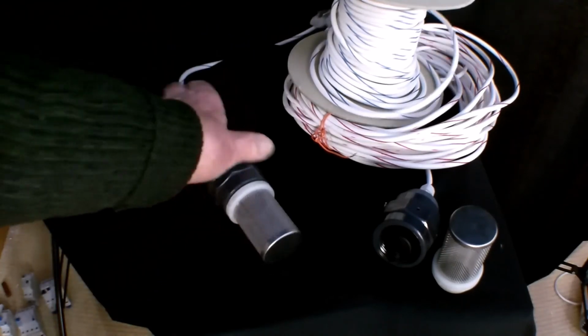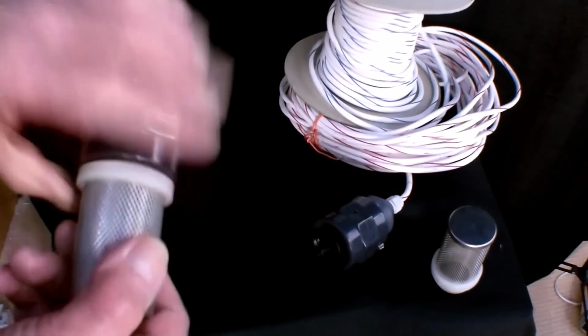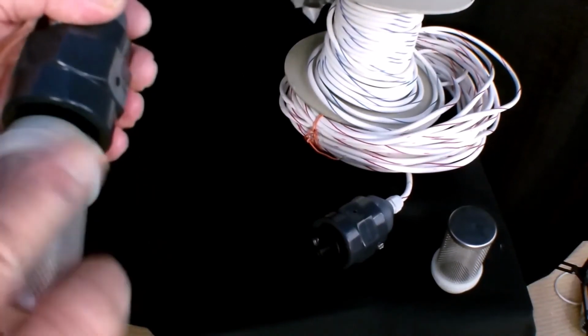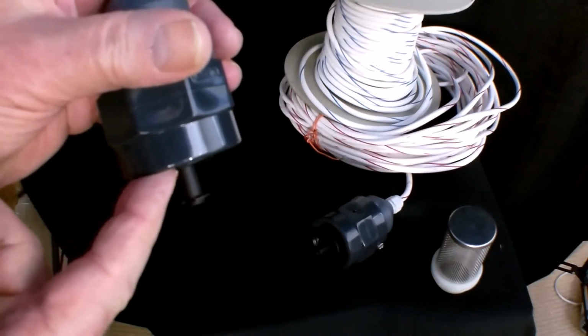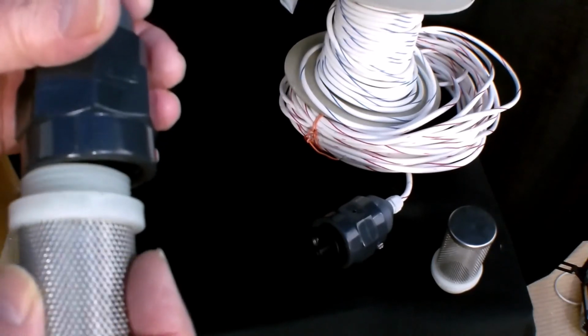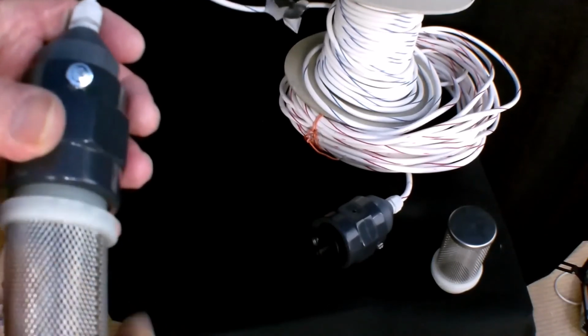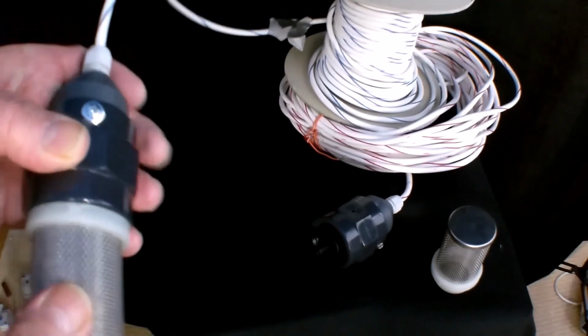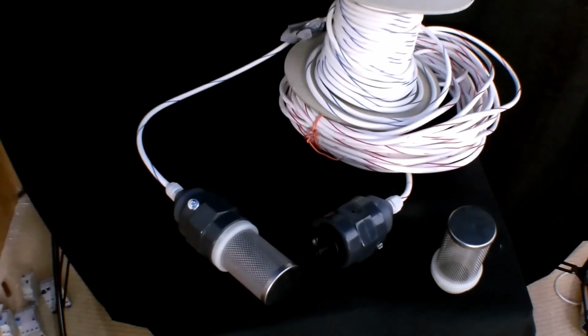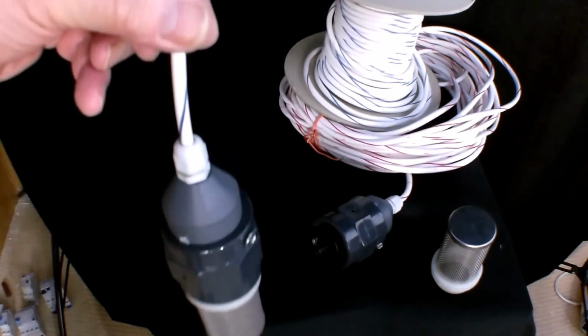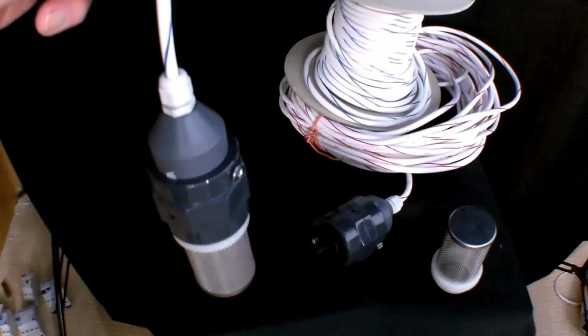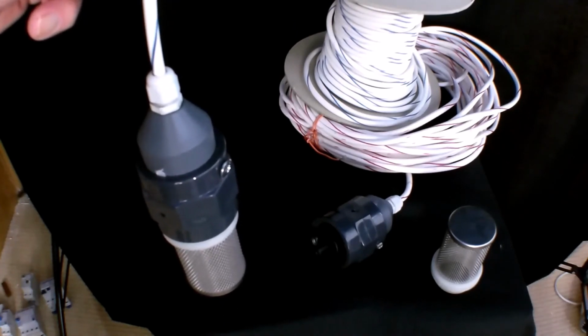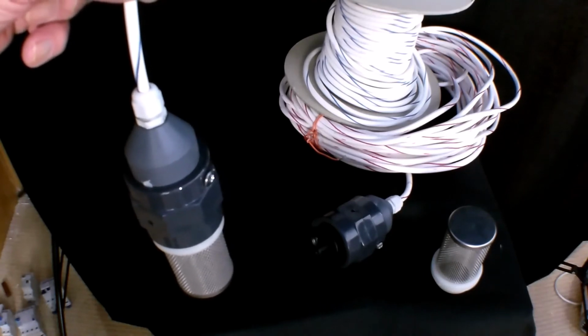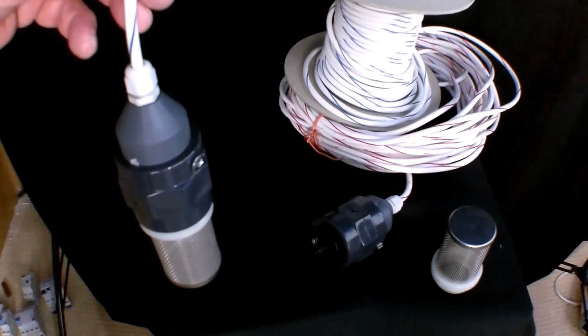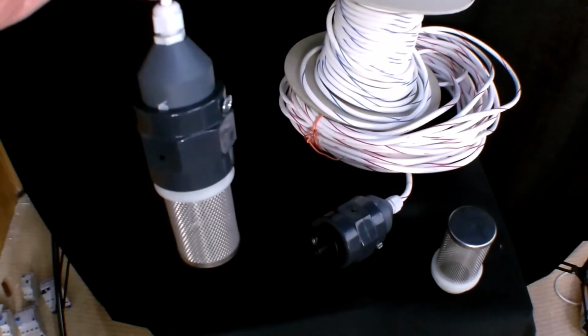The one over here is shown with the, I'll have to take it off here. This screen protects the actual float switch action, which is here. It has proved very, very useful. Most of the faults we get with float switches is usually hair or debris caught round the float, especially hair, and this has proved very successful to not having that as a problem. They're a pendant float switch, so you suspend them from anything that you like at the top of the tank. They can be used in balanced tanks or wastewater where you want to hold water for dechlorination for a period of time, and they've proved very successful.